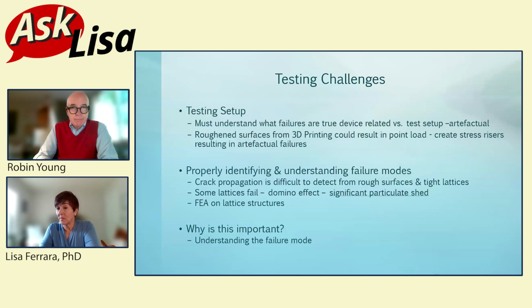And we put these, per the standard, in Delrin inserts. You test them statically, and you use Delrin. Well, Delrin's still pretty hard. It's harder than bone. So if the inserts that hold them in the test machine, those are the gripping fixtures, are not fitted properly, or you've got what we call point loading from the surface texture, you can get an early catastrophic dynamic failure. And you really need to understand that. It may not be related to the device, and that's not fair.